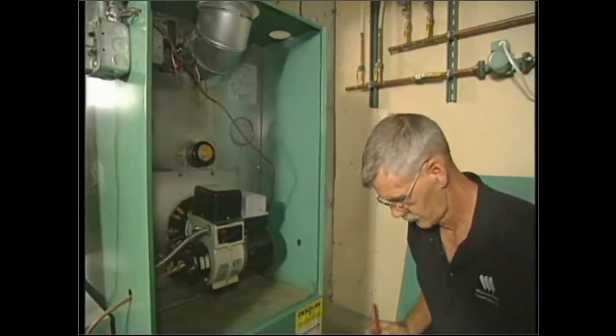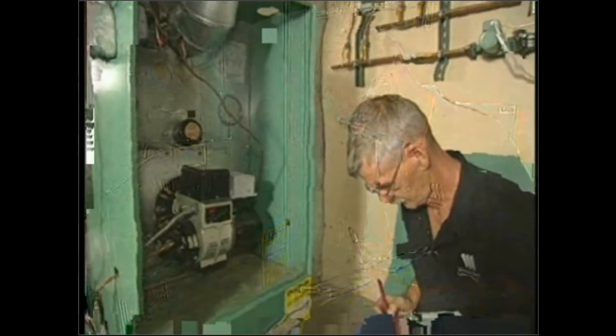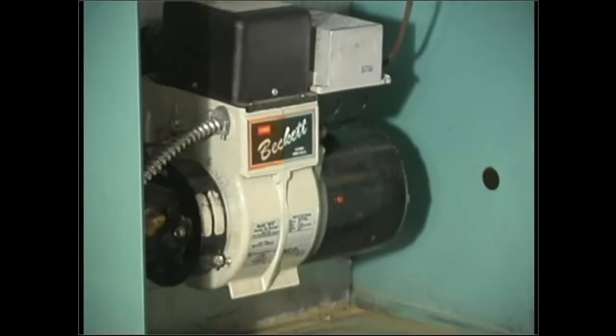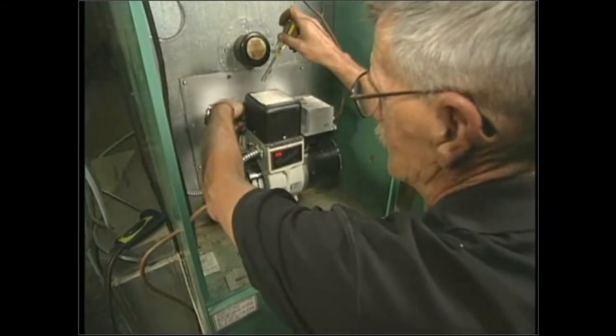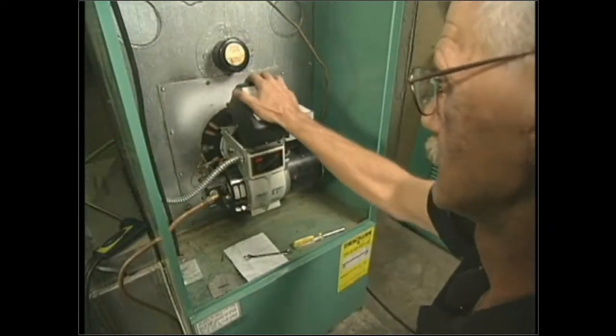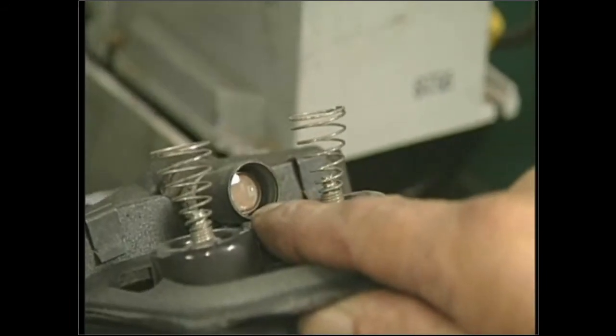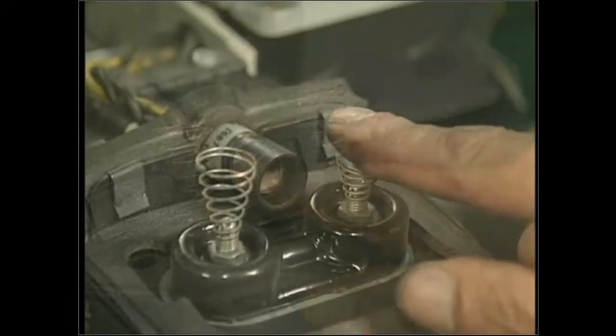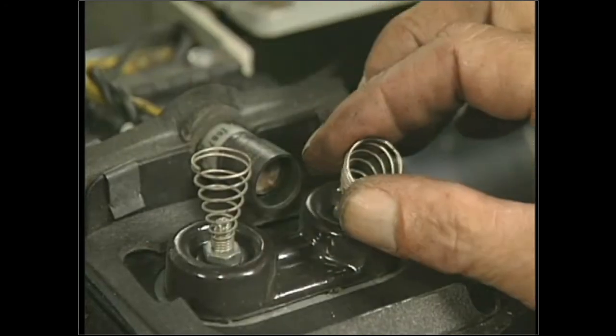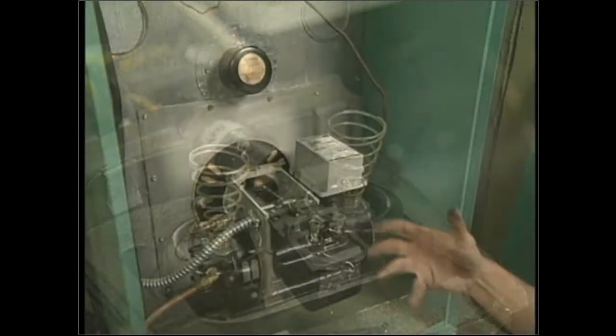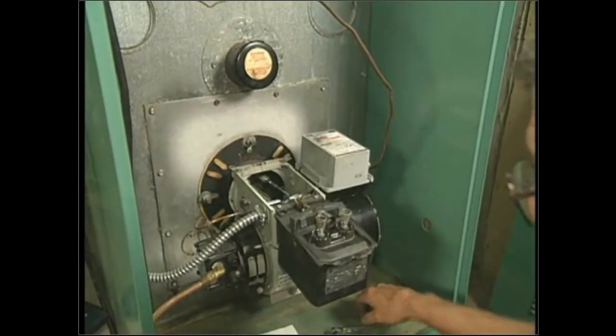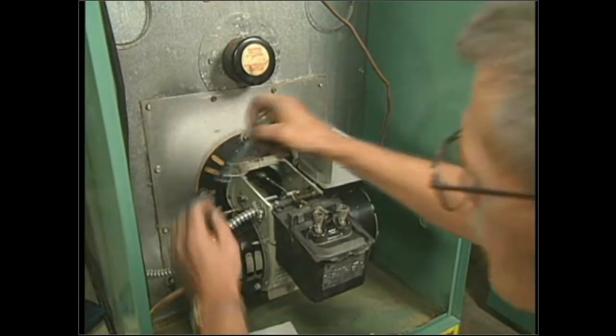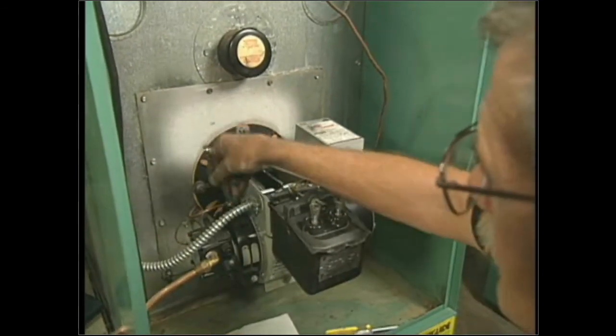Step 1 of the process involves a visual review of the transformer and should be done after evaluating the oil burner's initial operation and testing. Remove the transformer cover and start by inspecting the CAD cell for soot or a slight haze, which can cause the burner to misfire. Also, visually inspect the springs to make sure they are in good condition, and the blower wheel area for excess soot. The next step is to disconnect the oil line and remove the burner assembly.